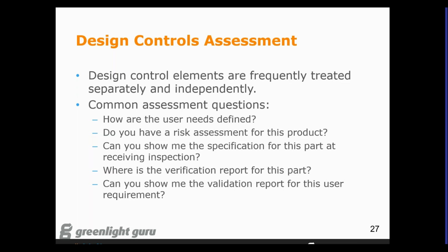Before, I initially would see very siloed approaches to these different elements, and the questions would be fairly straightforward within an element. How are your user needs defined? Can you show me the records? Can you pull those up? And you go through and you talk about user needs for a while. Okay, so you've satisfied that requirement within ISO 13485, or you've covered that element within 21 CFR 820.30, and you've checked that off, and you move on to the next element.